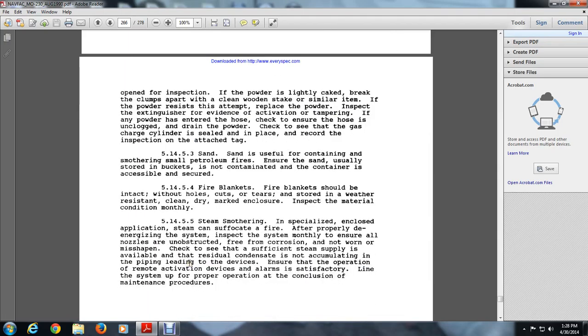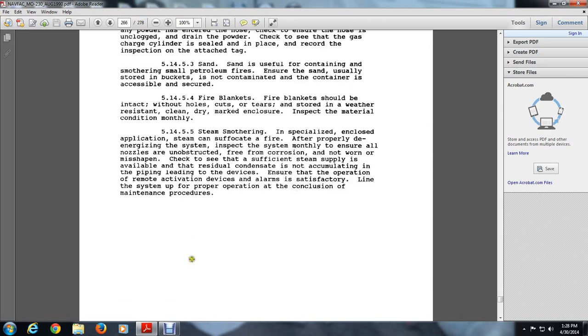514.5.5 steam smothering. Especially in enclosed applications, steam can suffocate a fire. After properly de-energizing the system, inspect the system monthly to ensure that all nozzles are not obstructed, free from corrosion, and not worn or damaged, and check to see that a sufficient steam supply is available. Ensure the operation of the remote activation device and the alarm is satisfactory, and the line system is in proper operation at the conclusion of the maintenance procedure.